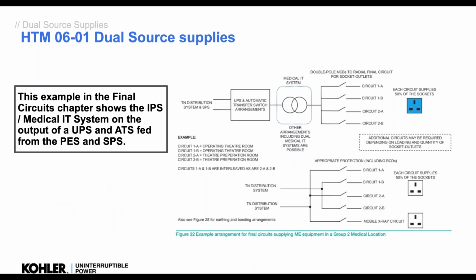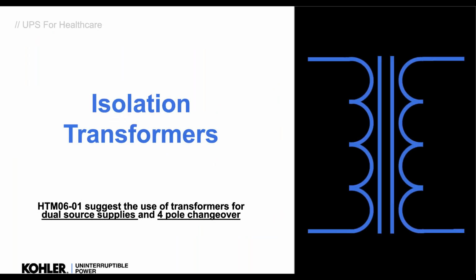So in this example, in the final circuits chapter, it does show a final circuit UPS with an ATS feeding a medical IT IPS circuit out to the theatres, which are interleaved on the output. It doesn't actually show where the ATS is. Is it here? Is it on the medical IT? Is it upstream? It doesn't really give that example, but we can decide how we need to do that for best.